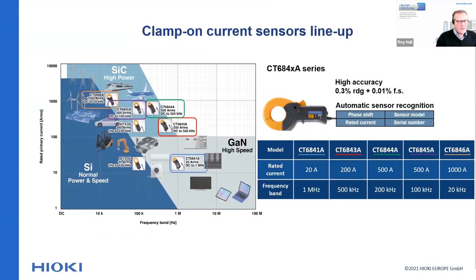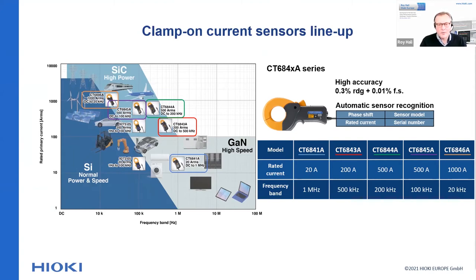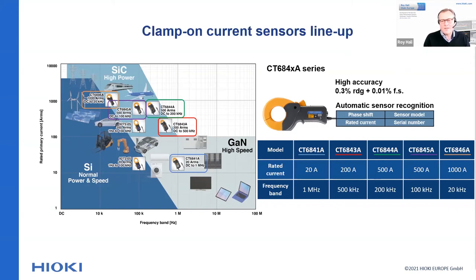Although clamp-on sensors might not seem the right fit for this high-spec power analyzer, the CT684xA series clamp-on sensors are worthwhile to consider. Their basic accuracy is 0.3%, and a wide operating temperature range of 0°C to +85°C makes them popular for WLTP tests of vehicles with an electrical drivetrain, as well as evaluation of solar power conditioners where bandwidth is not a critical issue.